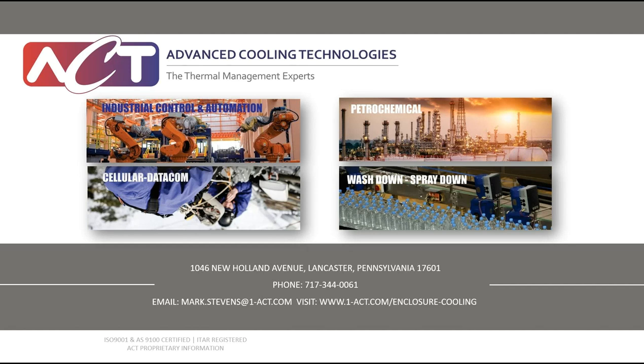What's the difference between the HSC and HPC heat exchangers? Okay, as I mentioned earlier, it's the heat transfer method. One utilizes a bonded fin technology, that's the heat sink cooler. And essentially, you're having impinging fans going on the inner cabinet and the outer cabinet to do the heat transfer. The other device is a heat pipe cooler, again utilizing that really high-value heat transfer method of using that heat exchange between going from a liquid to a vapor. That gives you a huge benefit on transferring heat from the inside to the outside. And the HPCs give you a little bit more density cooling package than the HSCs.